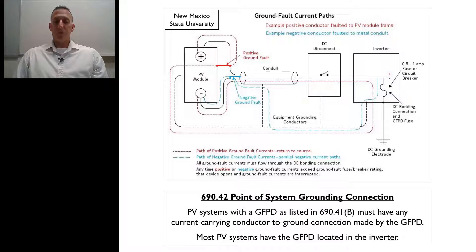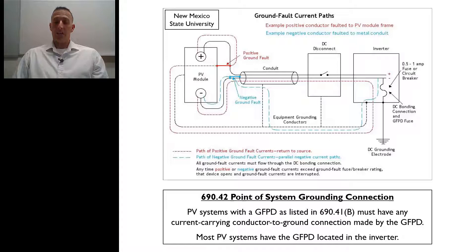In 690-42 of the 2017 National Electrical Code, it talks about the point of system grounding connection for solar PV systems. It states that PV systems with a ground fault protective device as listed in 690-41B must have any current carrying conductor to ground connection made by the ground fault protective device. So wherever you're connecting those current carrying conductors to ground, if you have a grounded system, that connection has to be made at the ground fault protective device.